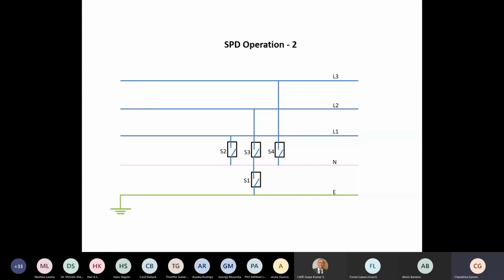And the other operation of an SPD is that imagine your earth potential goes up due to a nearby lightning. Now the S1 will go into low impedance mode, and then S2, S3 and S4 go into low impedance mode. Now your whole system is at high voltage. Say, for example, if the voltage at the earthing system goes to about 8 or 9 or 10 kilovolts, all your L3, L2, L1, N and E are nearly 10 kilovolts, so there will be no potential difference inside your equipment, although the whole potential has risen to a high value, so there will be no damage.